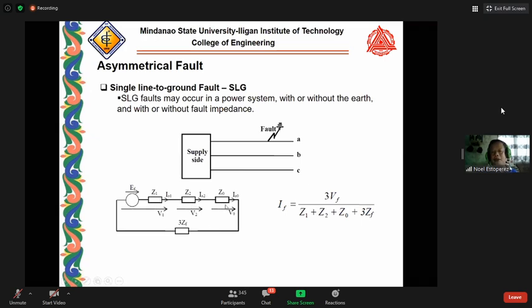The negative sequence and zero sequence are connected in series, and we have here a certain inclusion of the fault impedance. But if this is zero, we call this a bolted single line to ground fault. So this is now how it will be calculated.